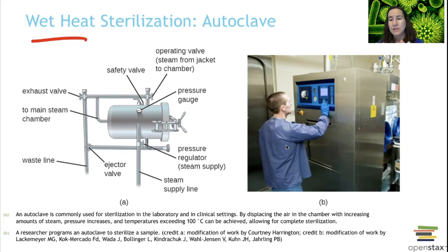So if you have a package of all of your dental hygiene tools, and I'm not dental hygiene, so I don't know the names of all the fancy tools, but you had them packaged up in your little kit, and you wrap it in the kit, and you put your autoclave tape on there, and you put it all in there. That other method with the vacuum sealing, where we suck out all the air first and then steam and pressure, will penetrate packages better than the other gravity displacement method. So different methods for different things.